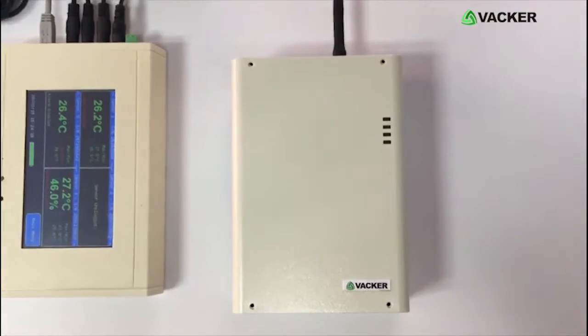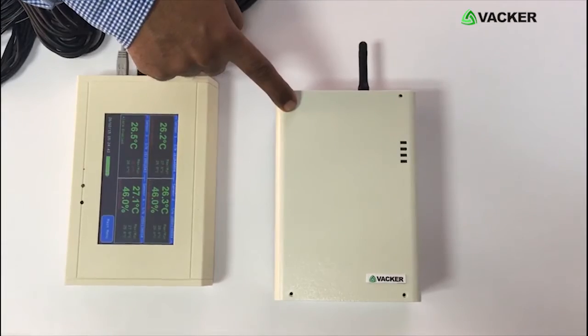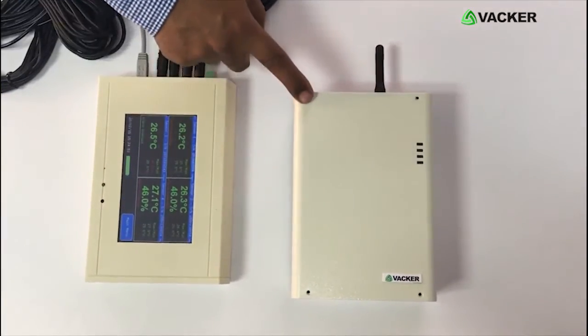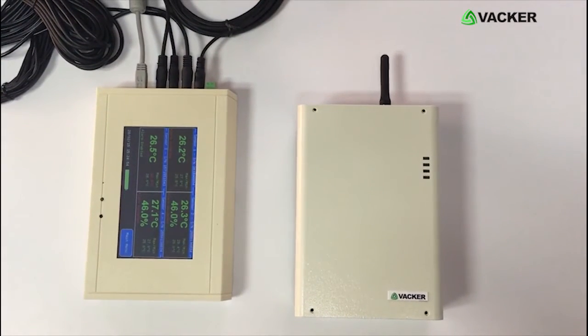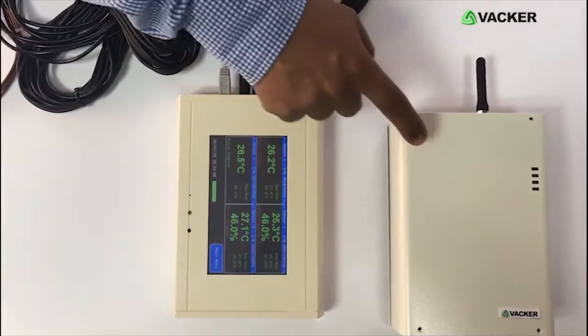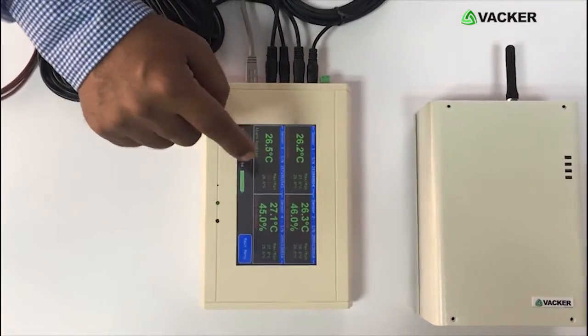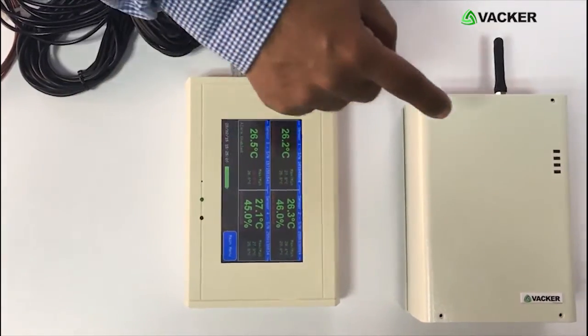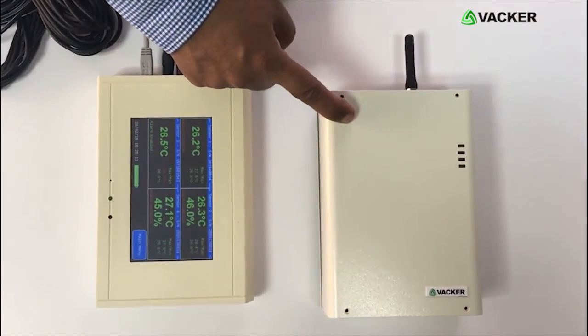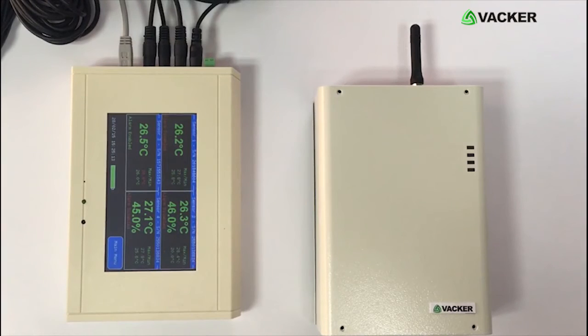This is the dialer which will make phone calls to 10 people. This has a SIM card and it is battery operated — it will work even in case of power failure, for a couple of days without power. This is the antenna of the device. From this recorder, you can connect the signal from this contact to this device, and in case the temperature goes above or below the programmed limits, it will give a signal that makes a phone call and SMS to 10 people. You can also connect power failure sensor, smoke sensor, water leakage sensor, door opening sensor, etc. to the same dialer.